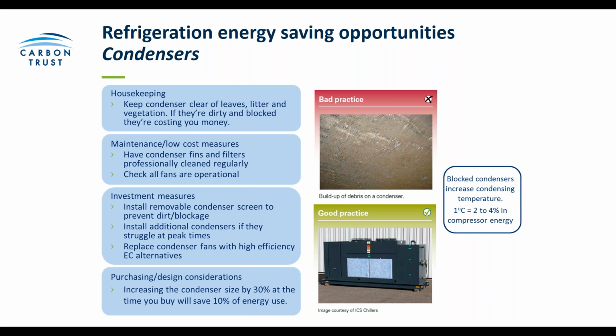When you're purchasing or designing a new system, look at getting a larger condenser than you normally would. Integrating a separate subcooling section will offer further savings of at least 8%. So having a larger condenser there than you normally would can give you some savings. And the newest condensers obviously have low energy fans and EC motors. So this will offer you significant power savings and the ability to control the system a lot better.